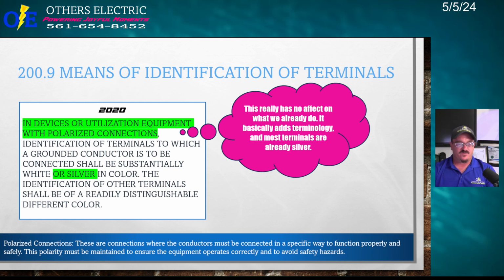All right, so the first major change pertaining to the residential in the 2020 NEC is the means of identification, 200.9, means of identification of terminals. It says in the 2020 NEC, in devices or utilization equipment with polarized connections, the identification of terminals to which a grounded conductor is to be connected shall be substantially white or silver in color. The identification of other terminals shall be of a readily distinguishable different color. This is really no effect, right?